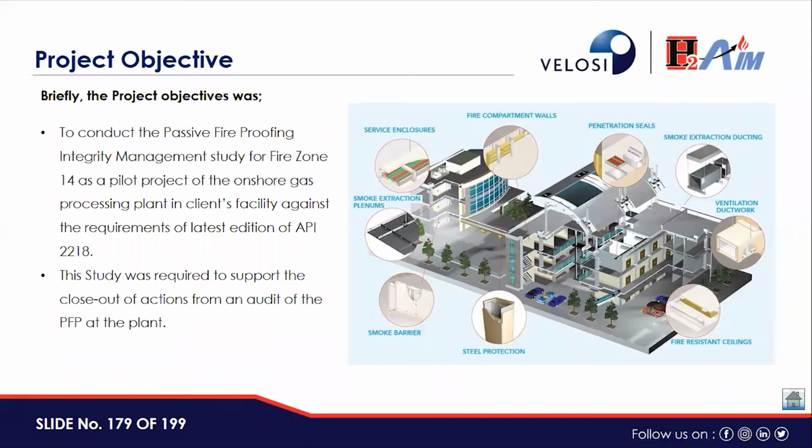To conduct the passive fireproofing integrity management study for fire zone 14 as the pilot project of the onshore gas processing plant in client's facility against the requirements of the latest edition of API 2218. This study was required to support the closeout of actions from the audit of the PFP, passive fire protection, at the plant.